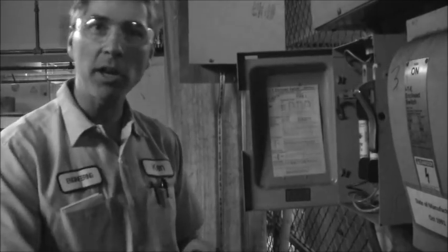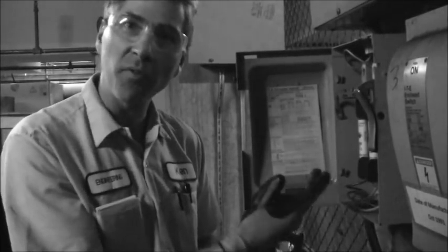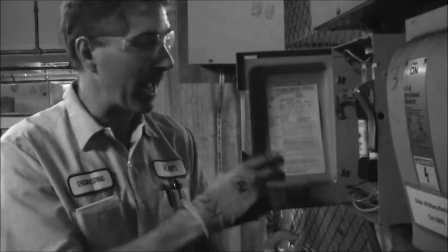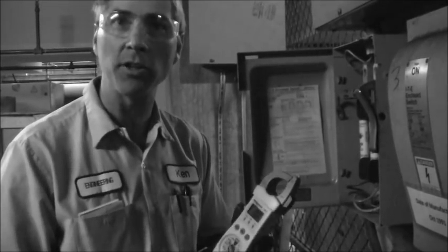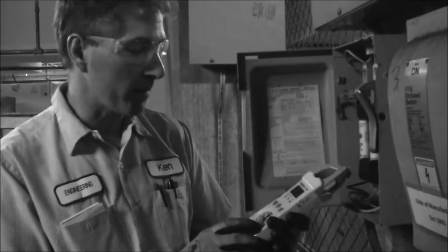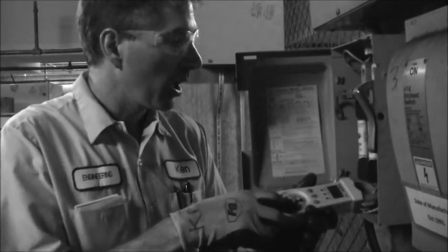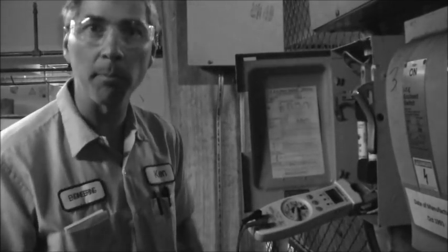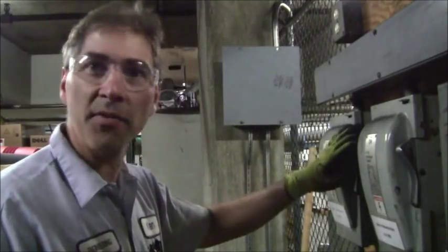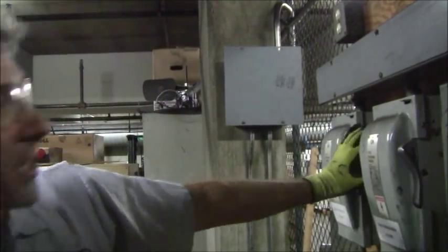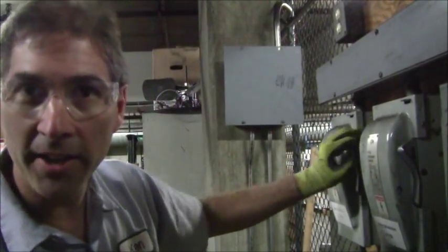So then I stopped the unit, shut it off, made sure I had no electricity. Then I put the phases back to normal, A, B, and C, the correct rotation. And then I'm going to show you what that looks like right now. We'll go ahead and do that demonstration. We'll put our meter on amperage, and we're going to go ahead and start this up. We're going to do that right now. Okay, we're going to turn this unit on, and just to be safe, I'm going to use my left hand. I'm going to kind of distance myself from the disconnect switch, and then I'm going to throw it on.